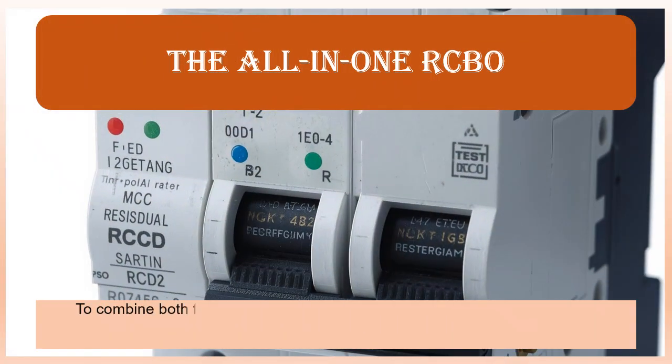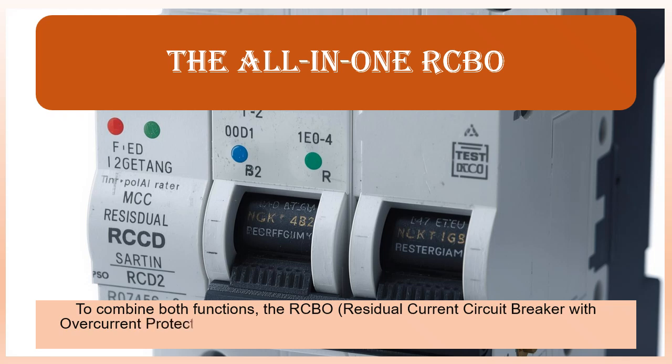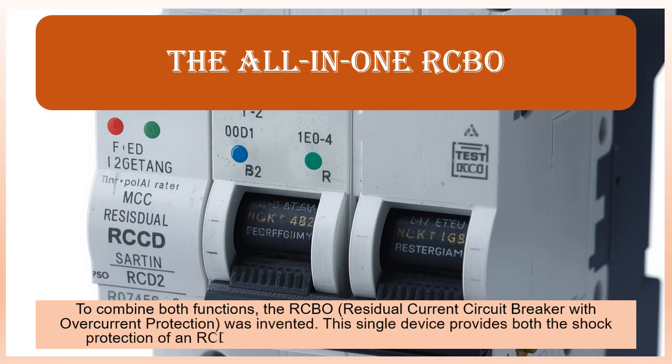The all-in-one RCBO. To combine both functions, the RCBO, Residual Current Circuit Breaker with overcurrent protection, was invented. This single device provides both the shock protection of an RCD and the overload short-circuit protection of an MCB.